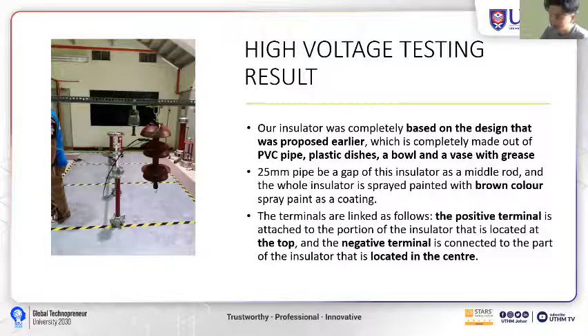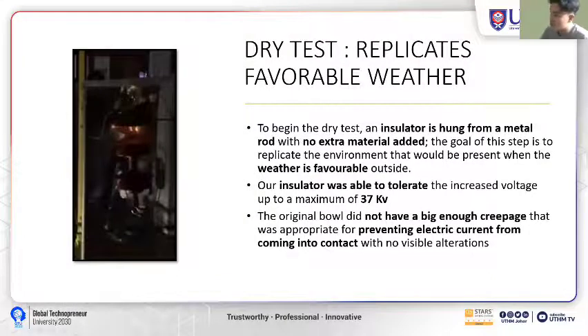During the high voltage testing, the positive terminal will be attached at the hook of the insulator, which is at the top of the insulator, and then the negative terminal will be connected at the rod, which is at the center of the insulator. The testing is split into the dry testing and wet testing. We'll proceed with the dry test. The dry test will replicate favorable weather. To begin the dry test, the insulator will be hung at the metal rod without any extra material, different compared to the wet test, where we will spray the salt water.